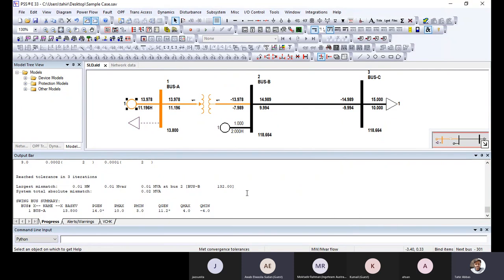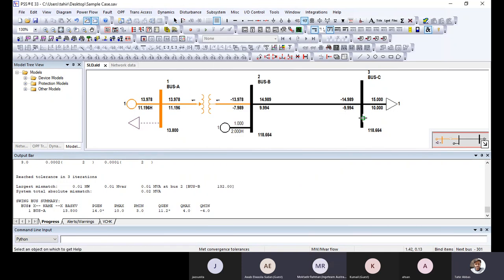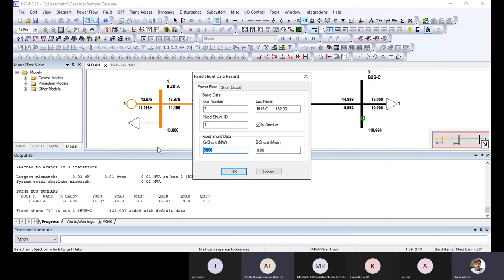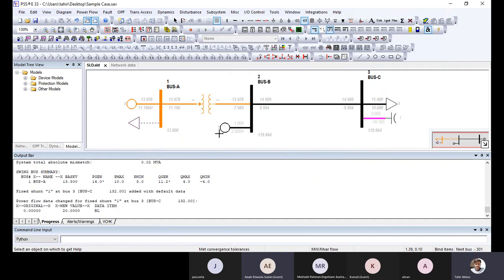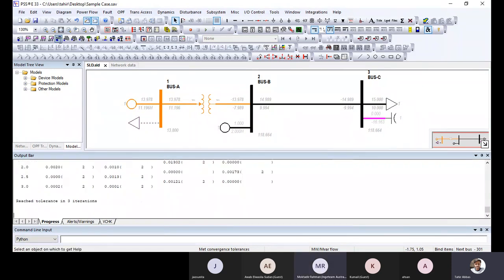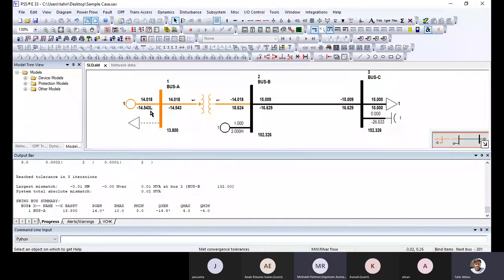In the same fashion, I have added a capacitor here near the load, a shunt of 20 megawatt. Now you will see the demand is 10 megawatt and I have added a 20 megawatt capacitor. You will see the reactive power back towards the generator is low. Can you see? Yes. It means that the generator is absorbing reactive power, so this is the under excitation limit.